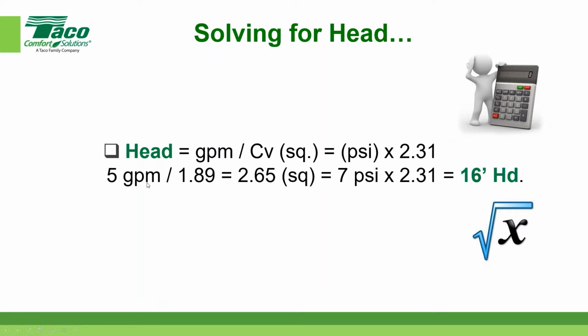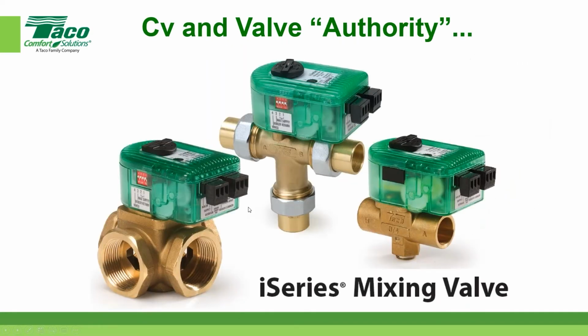Here's an example. 5 gallons a minute shoved through a device that has a CV of 1.89 is 2.65. Times itself, where we square it, is 7 PSI. 7 PSI times 2.31 is 16 feet of head. So again, this is how we use the CV to figure out how it's going to impact the circulator performance within a particular system. So hopefully that helps as well. We're not going to have time to wrap this up, but all I'm doing is expounding on what I've already just said. Just remember, the CV does impact the pump sizing.